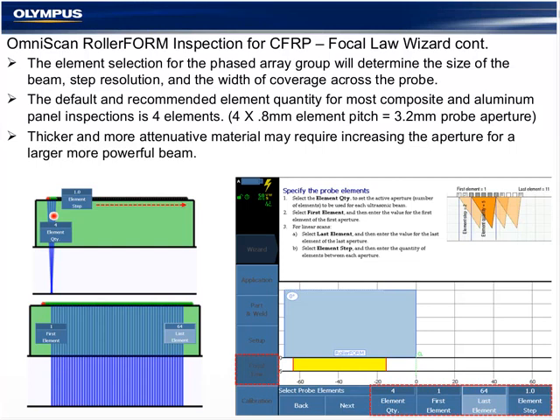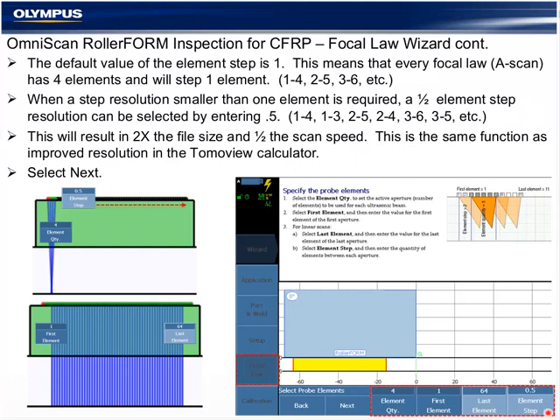So on the electronic or probe side, on the index axis, we have a 0.8 millimeter resolution, the pitch of the probe. And there's also the possibility of what's called improved resolution or half-step resolution. For a more precision inspection, where we want to step smaller than the pitch of the probe, entering 0.5 at this step will create a focal law or A-scan of 1 less element in between every A-scan, similarly to the previous slide. That has the effect of creating a simulated or electronic version of half an element. In that case, we would be stepping every 0.4 millimeters.